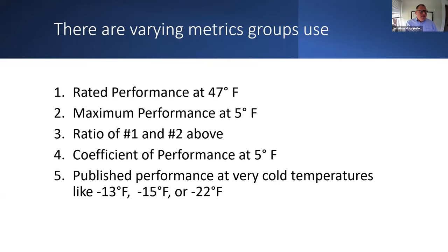The maximum performance at 5 degrees is a really important metric for cold climate heat pumps. At 5 degrees, we are cold. And the total capacity of a heat pump at that temperature, the maximum performance, is a really useful number. Most manufacturers, at least in their technical brochures, produce these numbers for consumers to look at. At the end of the day, a consumer buying a heat pump is buying a heating appliance, so knowing its total capacity at 5 degrees can be a useful number. Although the needs of the space, of course, will make that number most relevant. And so you need to know that piece of information to really put that maximum performance at 5 degrees to use.